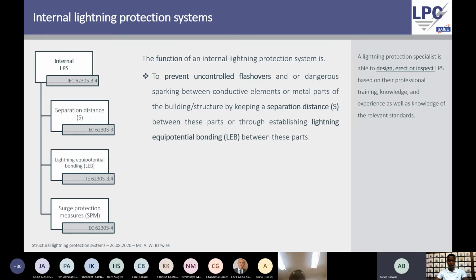or, as we have all learned, bonding. The standard speaks of lightning equipotential bonding between any metal parts. Lightning equipotential bonding will be explained a little bit later, but in essence we are trying to equalize any potential differences by a bonding method, either direct or indirect. Because if we equalize the potentials between two parts, we know that this prevents currents from flowing, and prevents arcing, sparking, and damage.